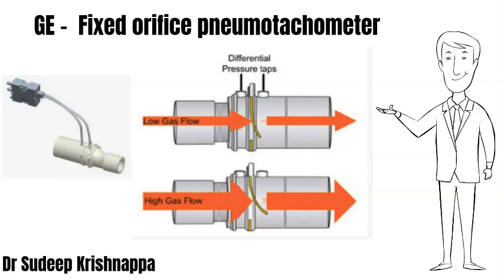Having a fixed orifice introduces a new set of problems. If the orifice is too small, it will be effective in measuring low flows as it can generate a measurable pressure drop even with low flows, but as flows increase it will act as an obstruction. Alternatively, if we have a large orifice, it will be effective in measuring high flows, but when the flow is low it will not generate an effective pressure drop, making it difficult to measure flow.